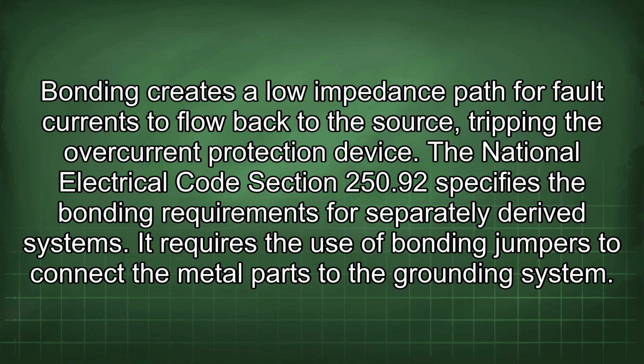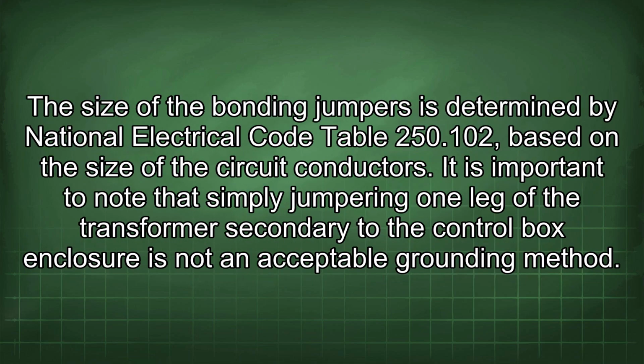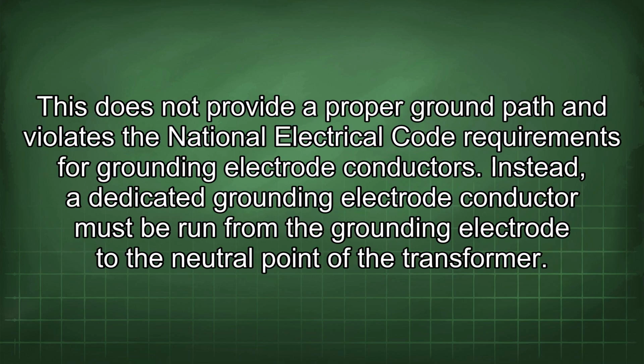The National Electrical Code Section 250.92 specifies the bonding requirements for separately derived systems. It requires the use of bonding jumpers to connect the metal parts to the grounding system. The size of the bonding jumpers is determined by National Electrical Code Table 250.102, based on the size of the circuit conductors. It is important to note that simply jumpering one leg of the transformer secondary to the control box enclosure is not an acceptable grounding method. This does not provide a proper ground path and violates the National Electrical Code requirements for grounding electrode conductors. Instead, a dedicated grounding electrode conductor must be run from the grounding electrode to the neutral point of the transformer.